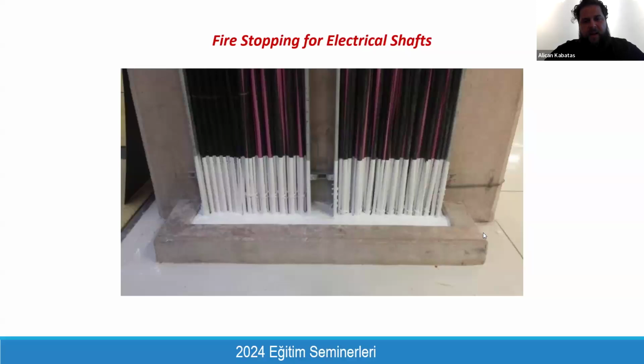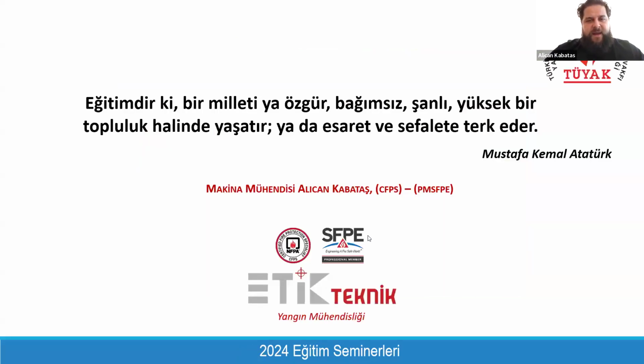And also, within the electrical rooms, you will have some electrical vertical openings, cable vertical shafts. And when the cable pulling is done, at the end of the day, before commissioning of the building, all of these cable shafts should be filled with 2-hour fire-rated fire stopping material, so that the compartmentation integrity can be achieved.